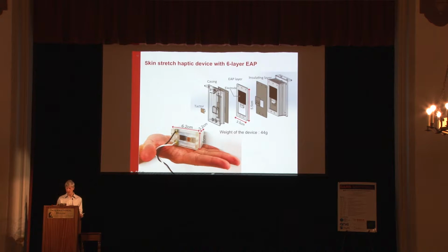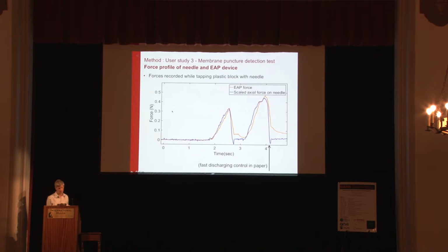It has to be MR compatible, of course, so we're using electroactive polymers. And to get the force level up, we use a 6-layer display for this very light handheld display. As you can see, it matches pretty well the forces at the tip of the needle. There are some tricks you have to do. This is a very viscoelastic material, so when you hit it with a high voltage, it responds initially pretty fast, but the relaxation is slower. So we have a special circuit to do some kind of fast discharging to relax it more rapidly.